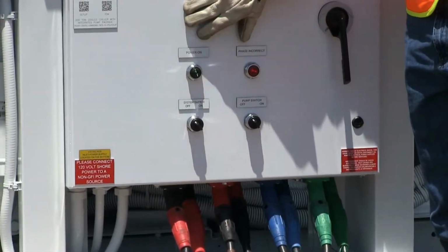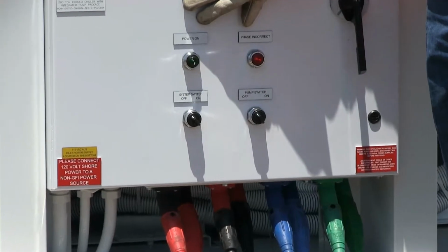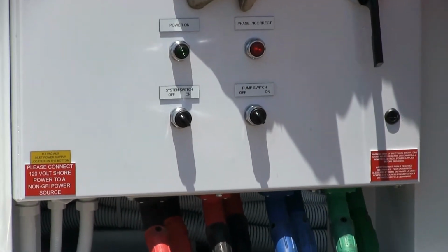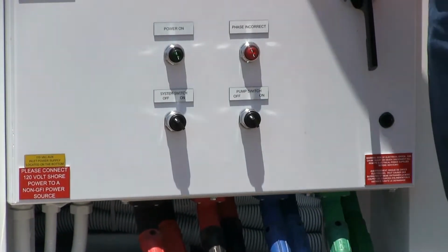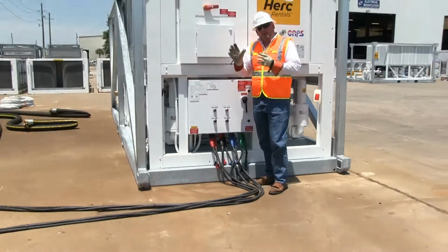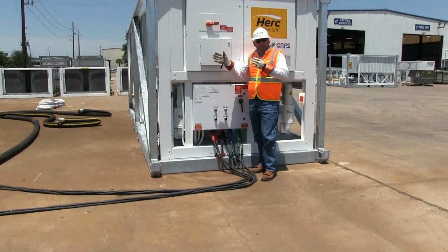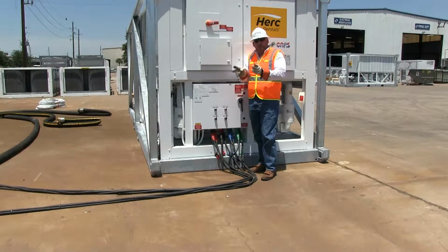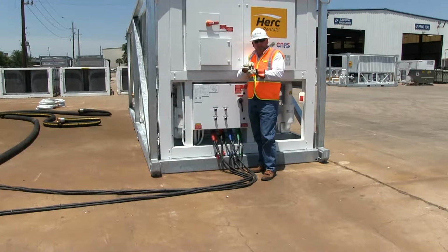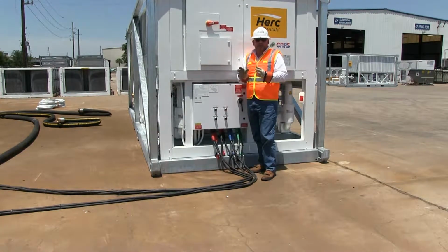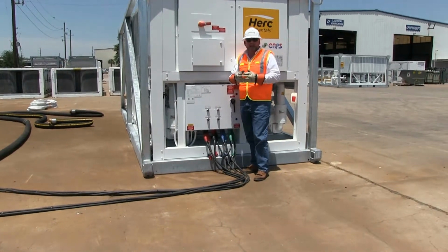There's a phase monitor inside the machine that prevents it from starting in reverse rotation. So we'll need to first turn the power off here at the chiller. We'll lock and tag out our power at our permanent power source, and we're going to have to swap two of our phases, A and B phase. Please note that you never change the Camlocks while the cable is energized.